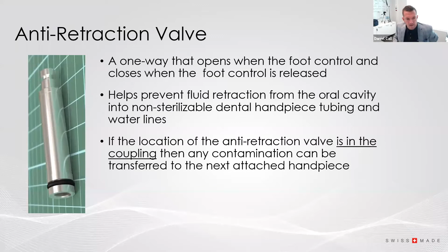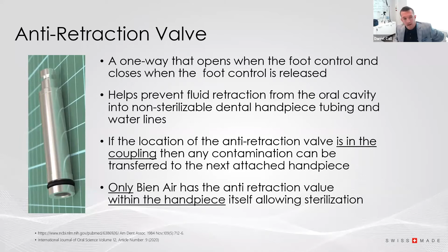So what happens is that over time, biofilm collects and gathers on everything that the water contacts. And there's retraction up to this valve, which is like the gate. Any contaminant or pathogen can latch itself to the biofilm. Just running the water in between patients isn't sufficient. The pathogen or contaminant can detach from the biofilm at any given time. So our design has always had the anti-retraction valve located in the handpiece. That means every time you sterilize a Bien Air handpiece, you're sterilizing the anti-retraction valve, and so any contaminant that is lodged onto the biofilm on that valve is sterilized.